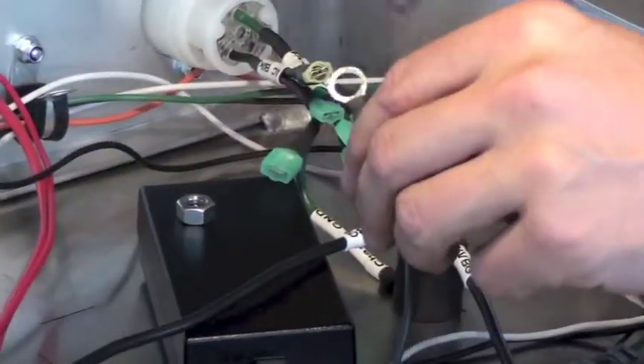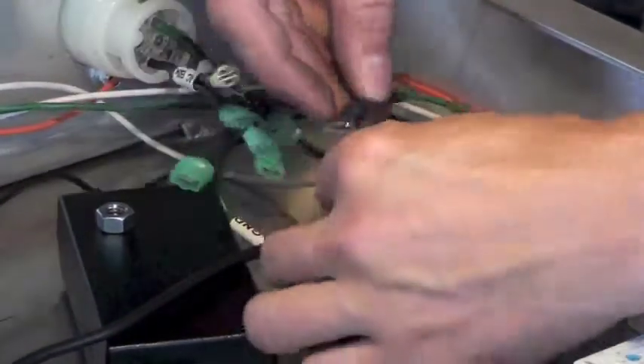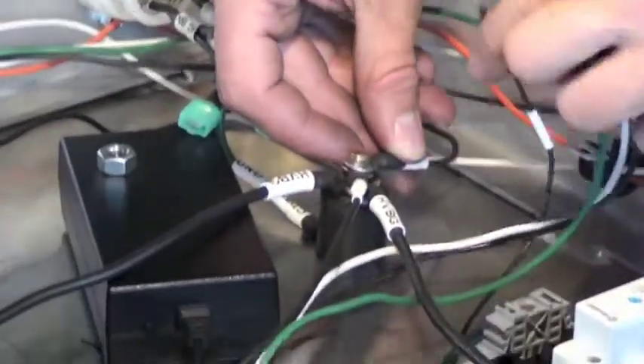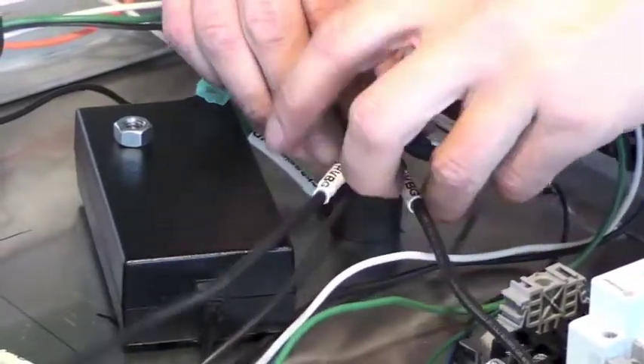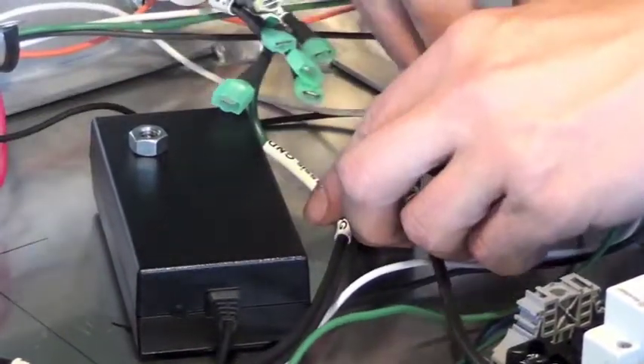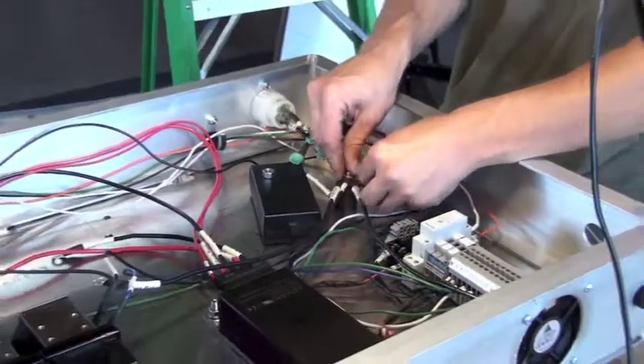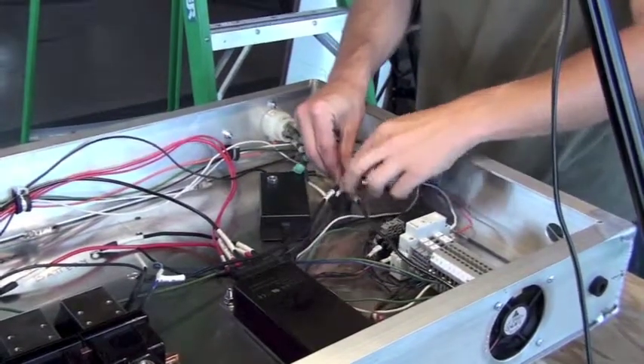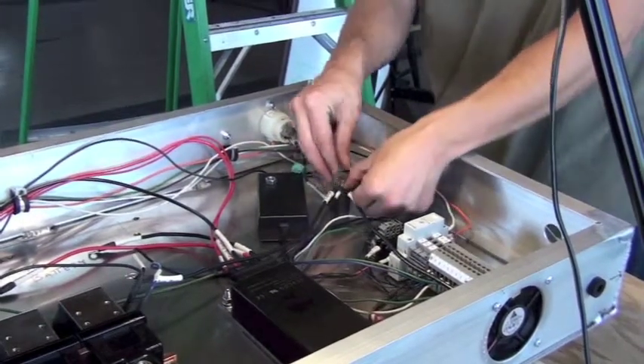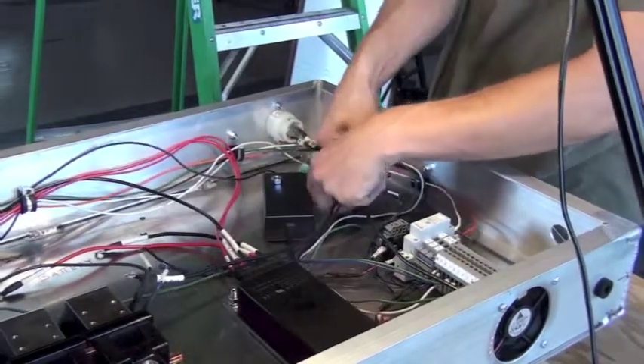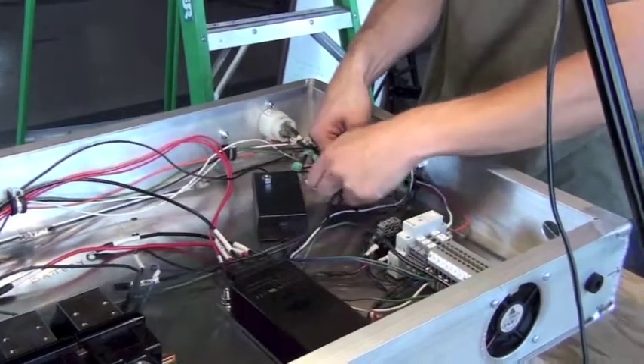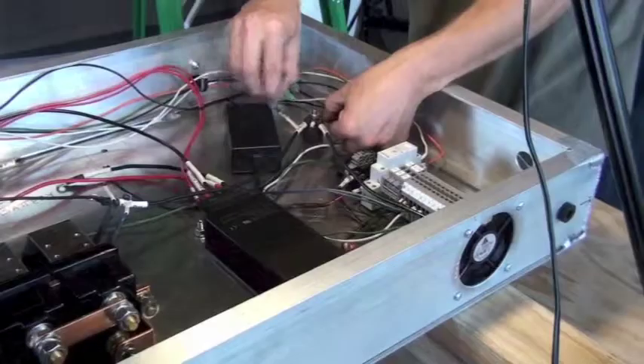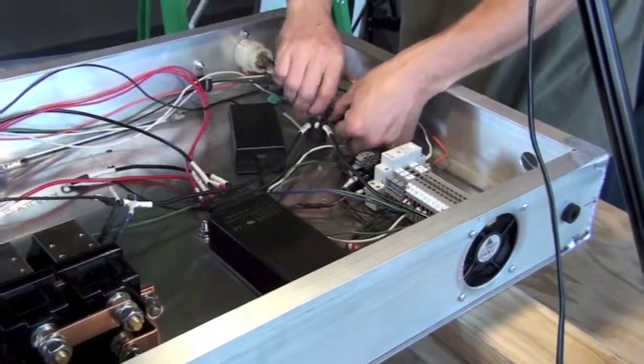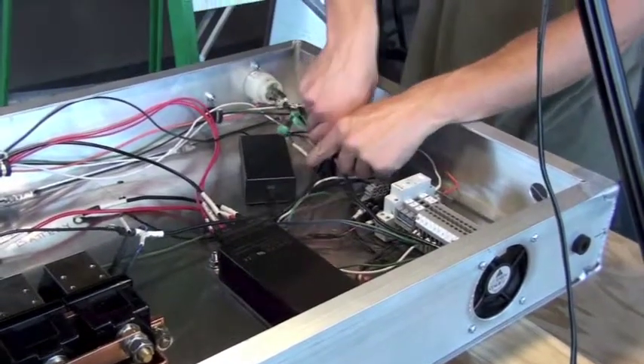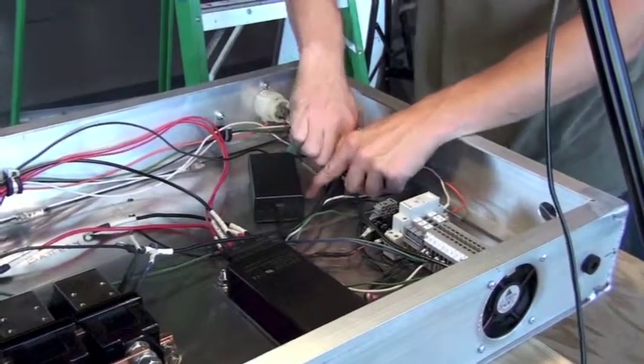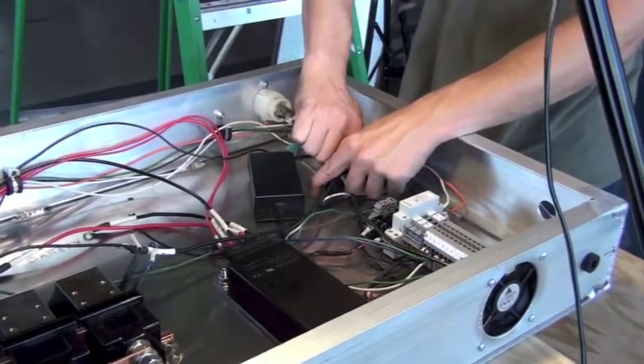When attaching wires to a common point, you want to make sure that the wire containing the most current is the closest to the source. So that's why we put the thickest wire on the bottom and then arrange the other wires according to the gauge of the wire and connections above it. And then we can tighten up our common ground, and this will complete the points that all get assembled to this common isolated ground point. You can spread these wires out a little bit too, fan them out a little bit so that they fit nice and snugly down on the common ground, and then tighten it up.